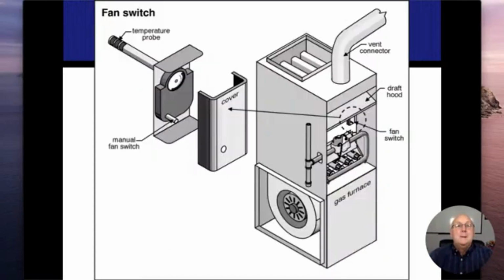So when we start getting into our forced air furnaces now, we need to start learning the different parts that we're going to be finding inside the furnace. All right. I talk about the temperature rise that we measure with those turkey thermometers or little dial thermometers, and this area up here, the ductwork that would be there, that would be called the plenum. And this is the area that I usually take that measurement.